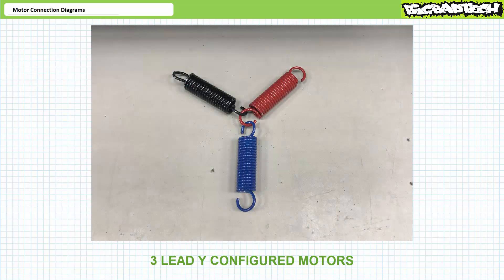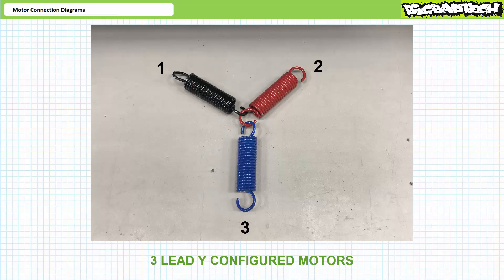Let's begin with an analysis of three-lead Y-configured motors. These motors are permanently pre-configured as Ys and there's nothing you can do about it. Electrically, one might visualize three separate windings permanently pre-bonded together in a Y fashion at a central node. Three external leads — one, two, and three — allow connection to primary voltage L1, L2, L3. Swapping any two applied phase sequences reverses rotational direction.